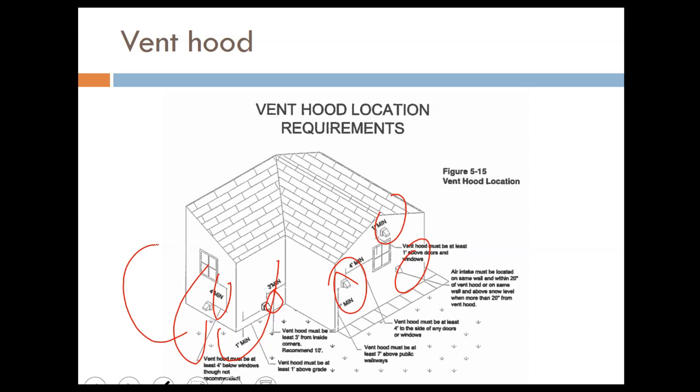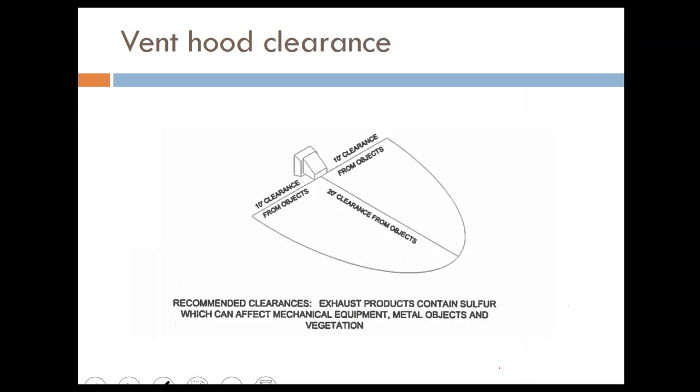And if it's going from the top of the window, it should be 1 foot, and this is according to NORA. And then you gotta check the regulation for your town, and the CMR for what the chimney termination from any opening in the house should be. I know from any opening it should be at least 4 feet, but there are different guidelines for where it can terminate, if it's the top of the window or below the window. So make sure you review the CMR for that information.